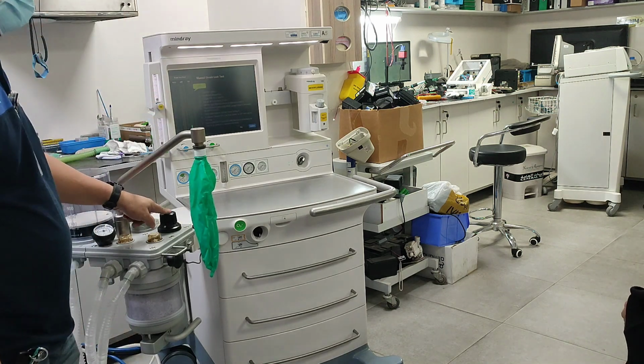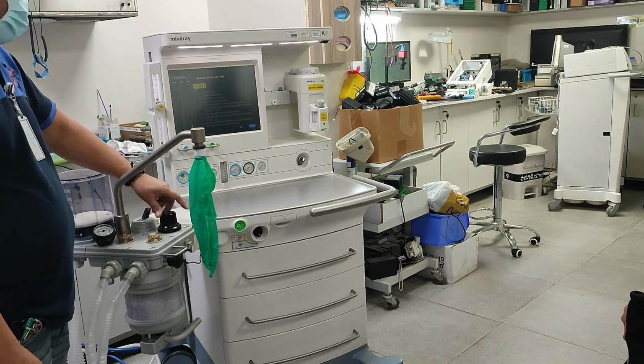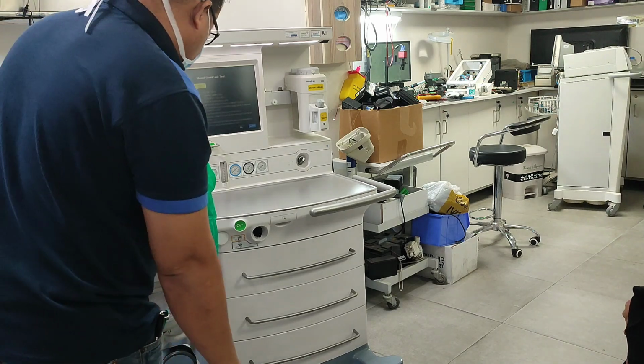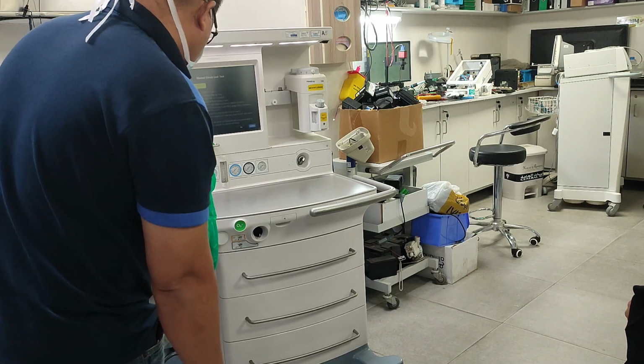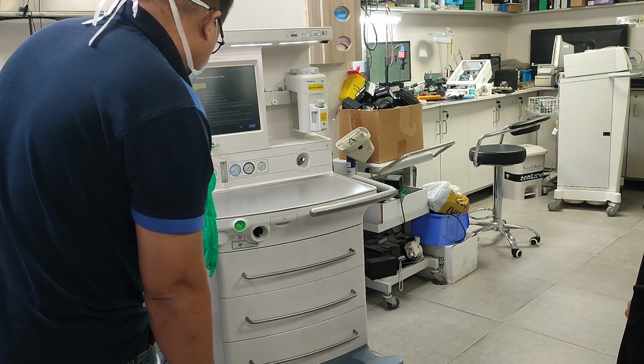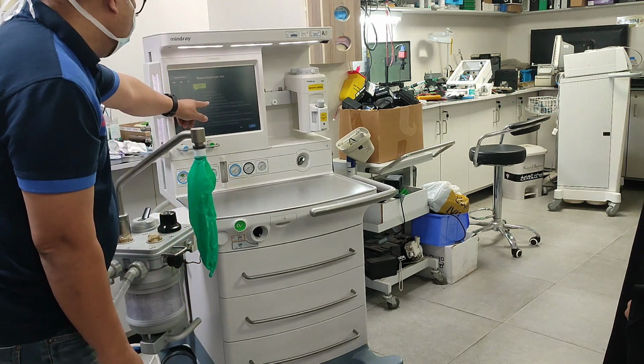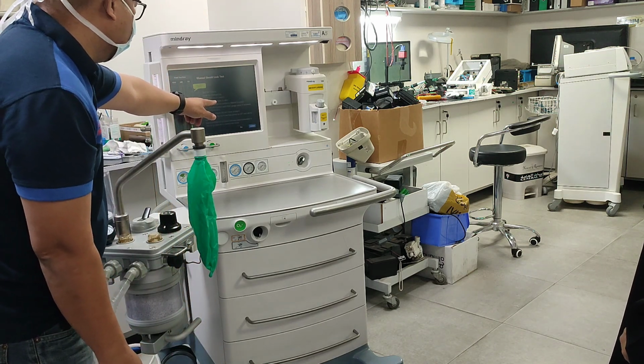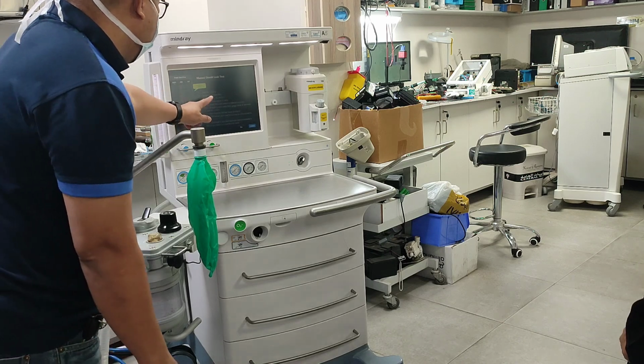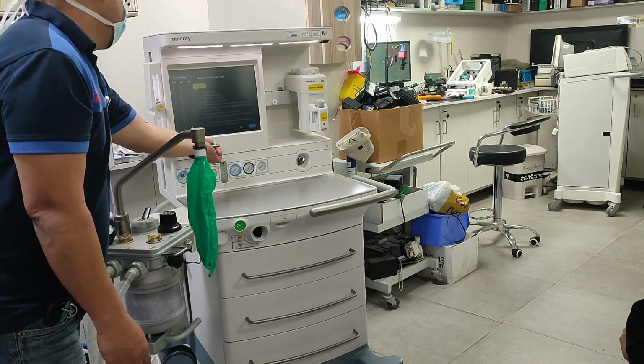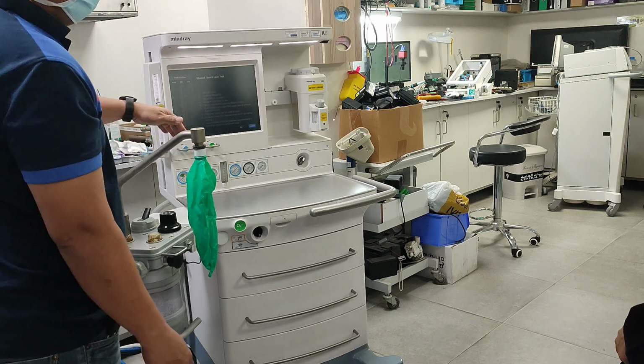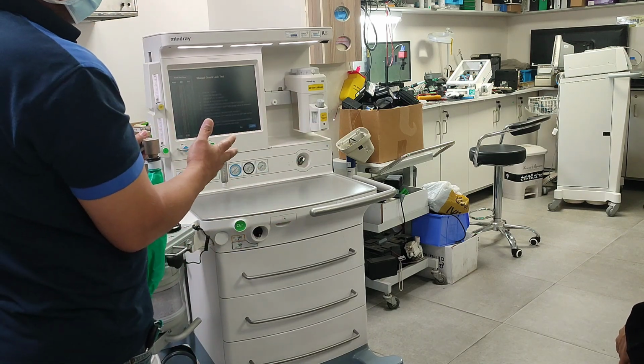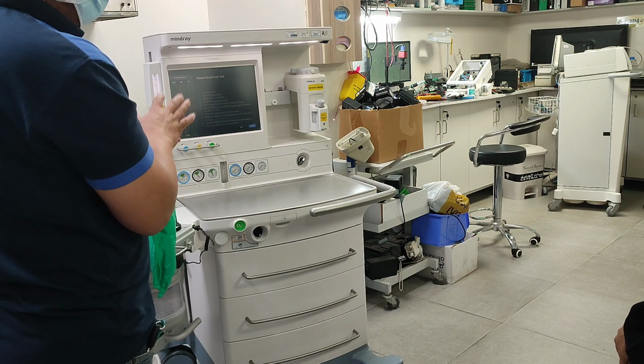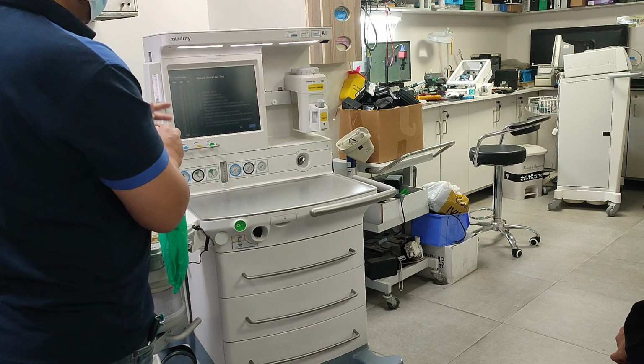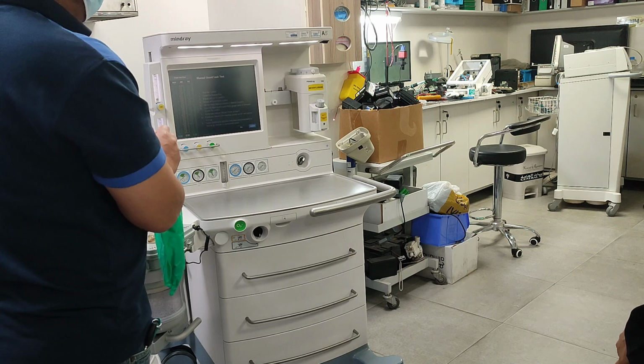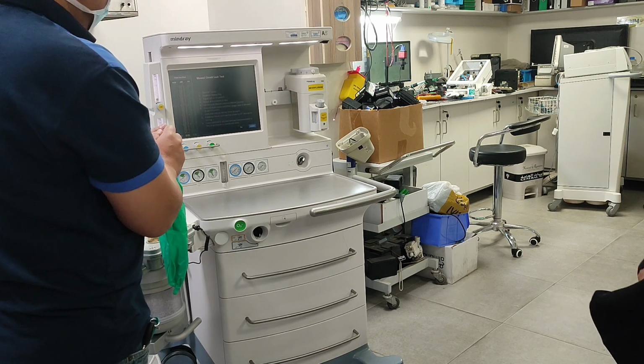So this is the APL. Tighten it here, APL. See? You just adjust it to 75, between 50 and 75 centimeters of water. Then adjust all flow meters to 0. So you should make this one 0. All should be 0. There is no flow of oxygen or gases. There should be no flow of air or oxygen during the basic check, because we are checking the internal components inside.